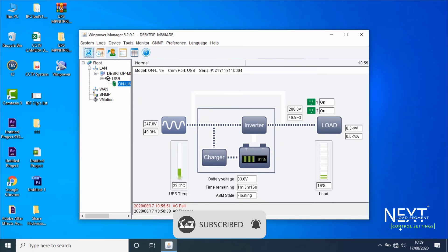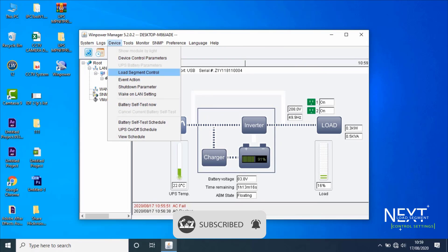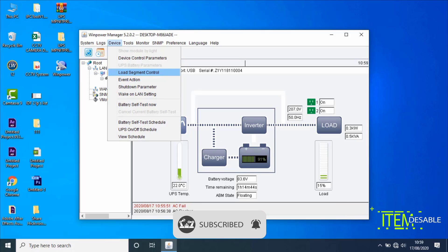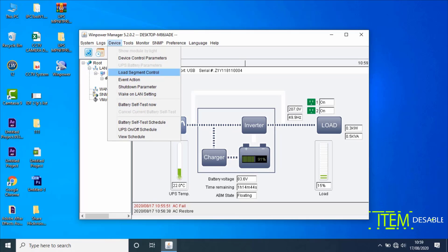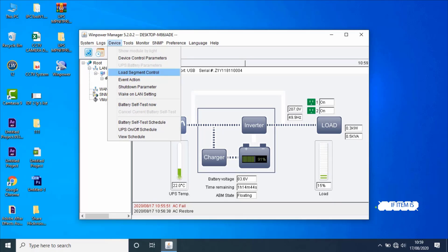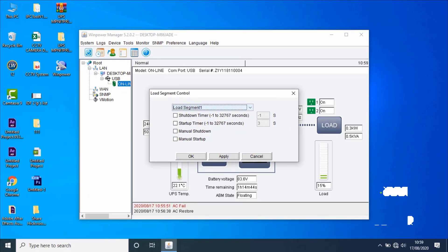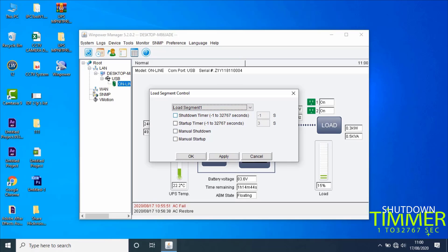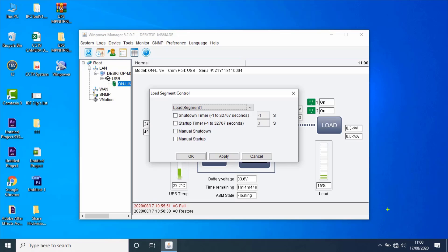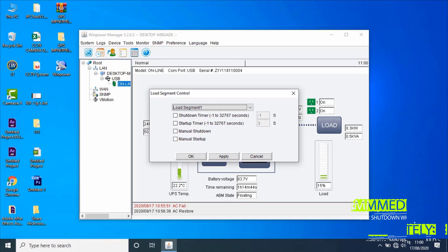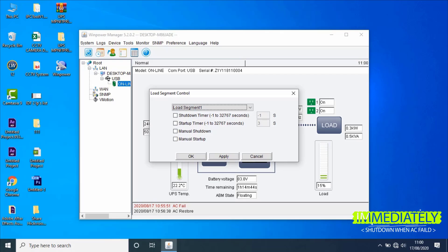Go to the next option — load segment control settings. If you select the UPS node and try to find load segment control settings from the menu and the item is disabled, that means the UPS doesn't support the load segment function. If the item is enabled, the UPS supports it. When the shutdown timer is -1, the load segment won't shut down automatically when AC fails. When the shutdown timer is 0, the load segment will shut down immediately when AC fails.